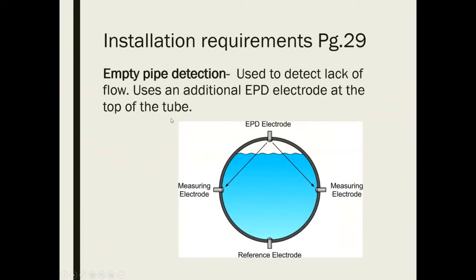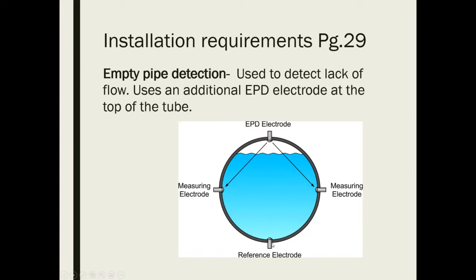Empty pipe detection: having the pipe empty is bad, especially when the unit is powered on. Some mag meters have empty pipe detection electrodes that compare against a reference electrode at the bottom of the pipe — if they get the same electrical signal the pipe is assumed full; if they differentiate, the pipe is assumed empty. When shutting down, turn off the mag meters before draining the piping system to avoid burning out the coils.